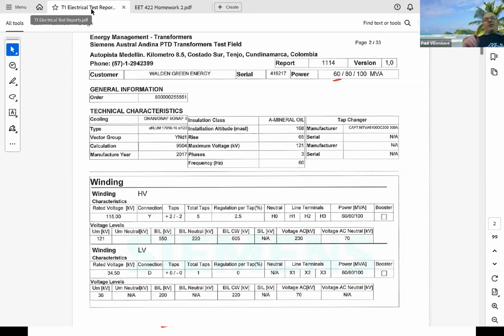So when you're looking at your data, here's the key thing. This right here is going to have the load loss test. And this is going to be the no load test. So you have to make sure that you're going to reflect the impedances to the same side, either the high voltage side or the low voltage side when you do this work. Okay. And there's some other things when you look at the test reports, you'll see some different data. If you think about it and you come up with a reasonable assumption, I'll probably be okay, but there's one very obvious one. What I'm trying to do is give you a lot of practical, like why you do things. And this is, again, exactly how all these devices are tested. You'll even see that in this test report, how they do it exactly the way we talk about in class, just because practically it's much harder to do things the other way around.